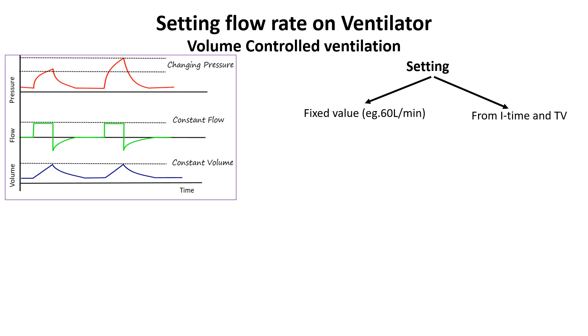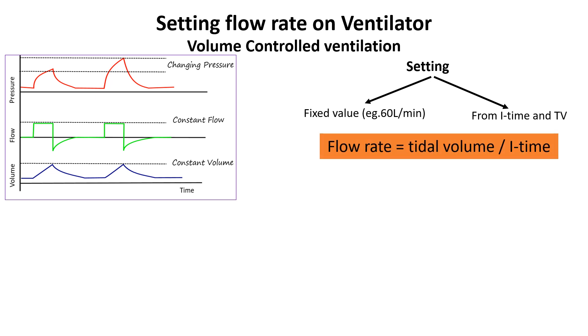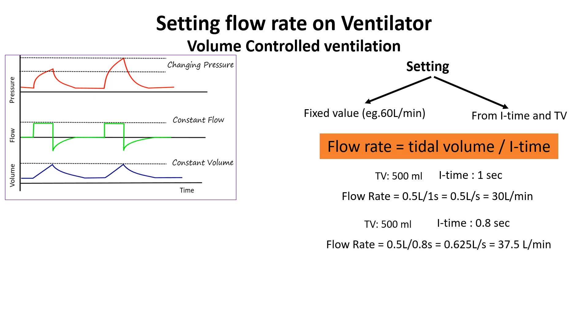The flow rate depends on the ventilation mode, patient condition, and clinical goals. In volume-controlled ventilation, flow rate can be set manually as a fixed value, or adjusted indirectly by setting tidal volume and inspiratory time, which the ventilator uses to calculate the required flow. For example, if the tidal volume is 500 mL and the inspiratory time is 1 second, the required flow rate is 30 liters per minute. If the inspiratory time is shortened to 0.8 seconds, the flow rate must be increased to 37.5 liters per minute to maintain the set tidal volume.